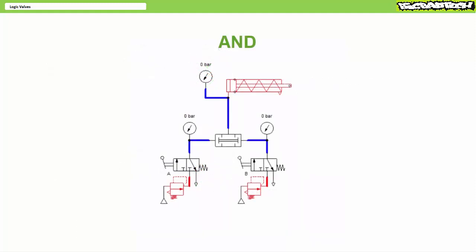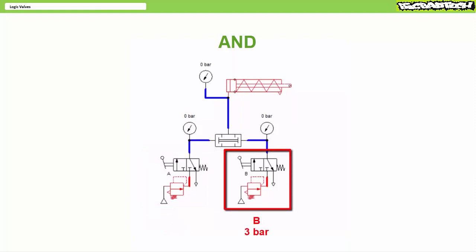A simple test circuit can be used to demonstrate the function of these two logic valves. Let's take a look at the AND or dual pressure valve first. The regulator on the left is set to 2 bar, or roughly 29 PSI. The valve on the left blocks or passes the signal to input A. The regulator on the right is set to 3 bar, roughly 43.5 PSI. The valve on the right blocks or passes the signal to input B.